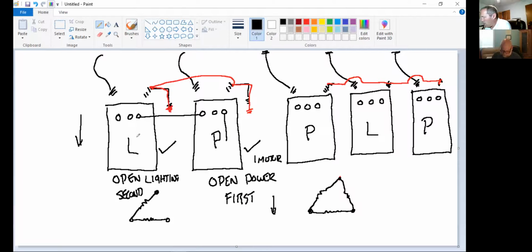Try to compensate for that one? Exactly, it'll try to compensate for all of the load, not only itself, but the lighting load also. If you pull off the lighting load first, you're either going to melt the fuse out, or, remember, we've got a tie-in bus going through here, it's trying to pick up all the load at once, or you're going to roast the transformer in the process.